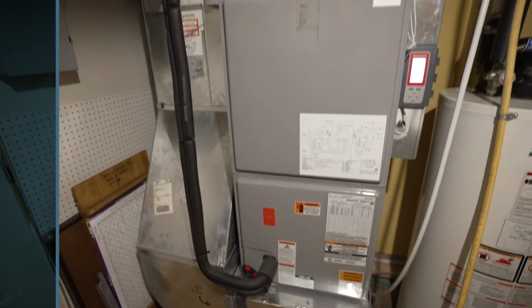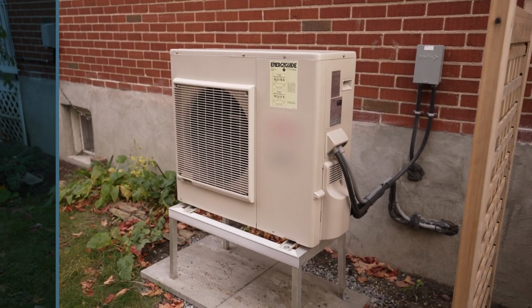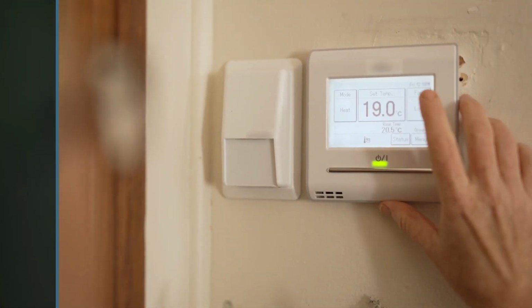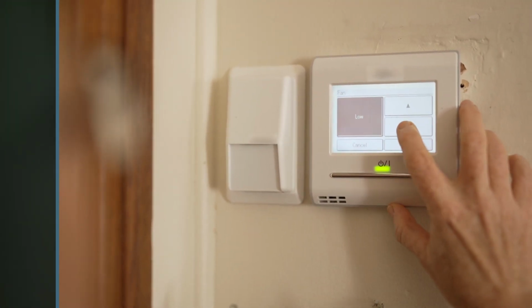We found that the performance of the cold climate heat pump was surprising. The comparable output size was 1/2 to 2/3 less than that of the furnace, and still able to provide the required heat. I should stress that the investment in weatherization and air sealing really paid off for this customer.